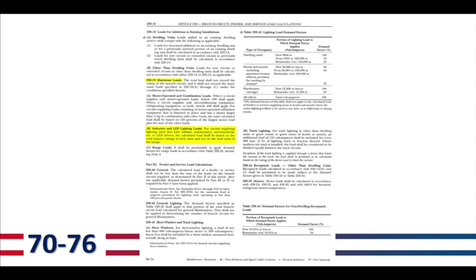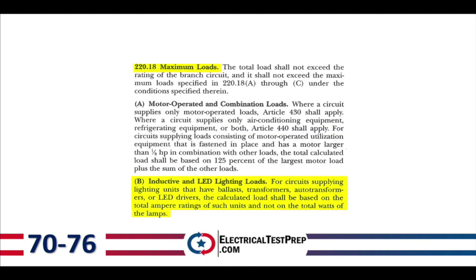On page 76, top of the left-hand column, section 220.18 Maximum Loads, letter B — Inductive and LED Lighting Loads. For circuits supplying lighting units that have ballasts, transformers, auto-transformers, or LED drivers, the calculated load shall be based on the total ampere ratings of such units, not the total watts of the lamps.